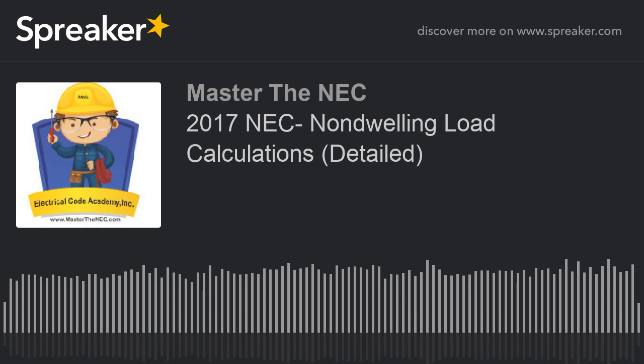We applied 70% to the amount that was over 200, and that was 207 amps, and that was our neutral load. Now, let's use a little bit of caution here when we're understanding the reduction of the neutral's capacity and what we can and what we can't do. This 70% reduction that can be applied only applies if the system is a single-phase AC or a 4-wire 3-phase system or a 3-wire 2-phase system or a 5-wire 2-phase system. Then I can apply this application, all right?